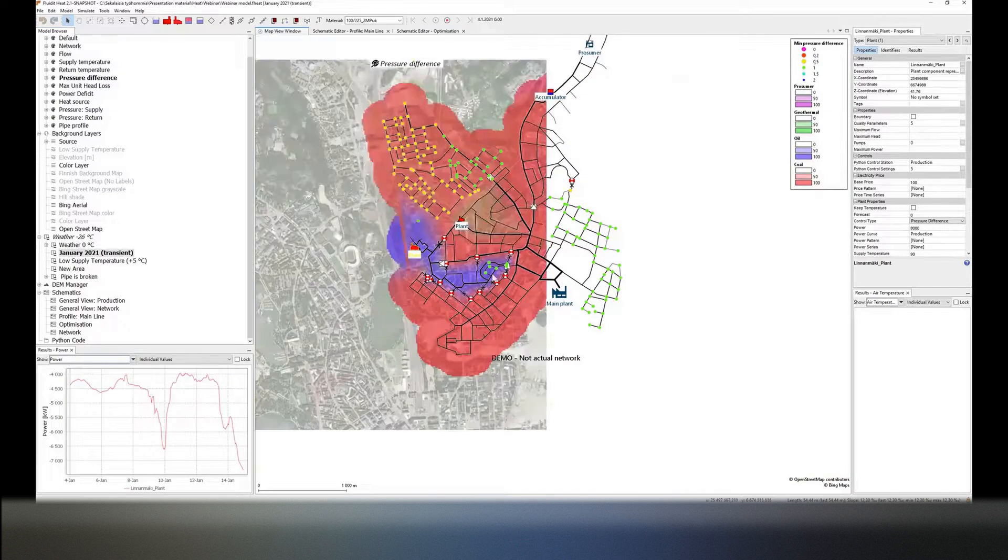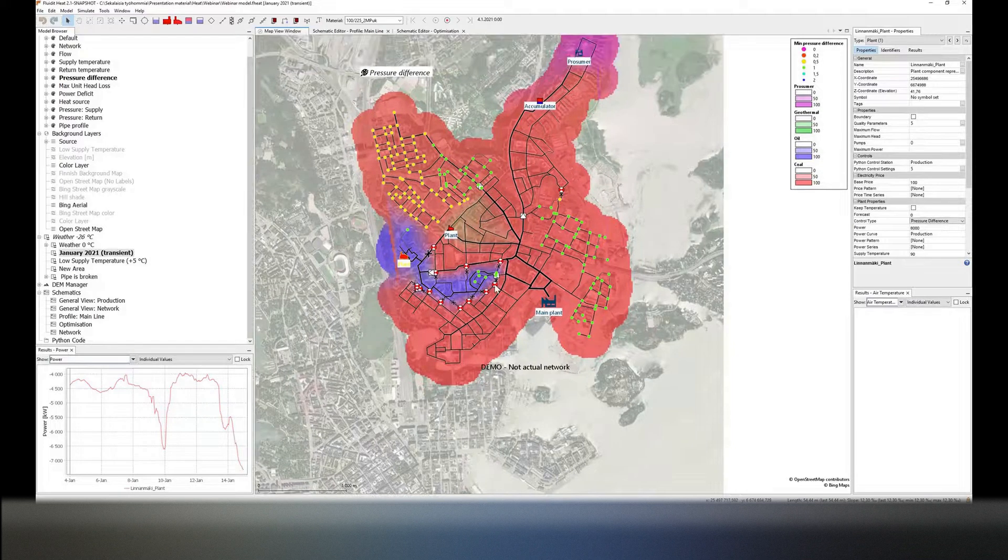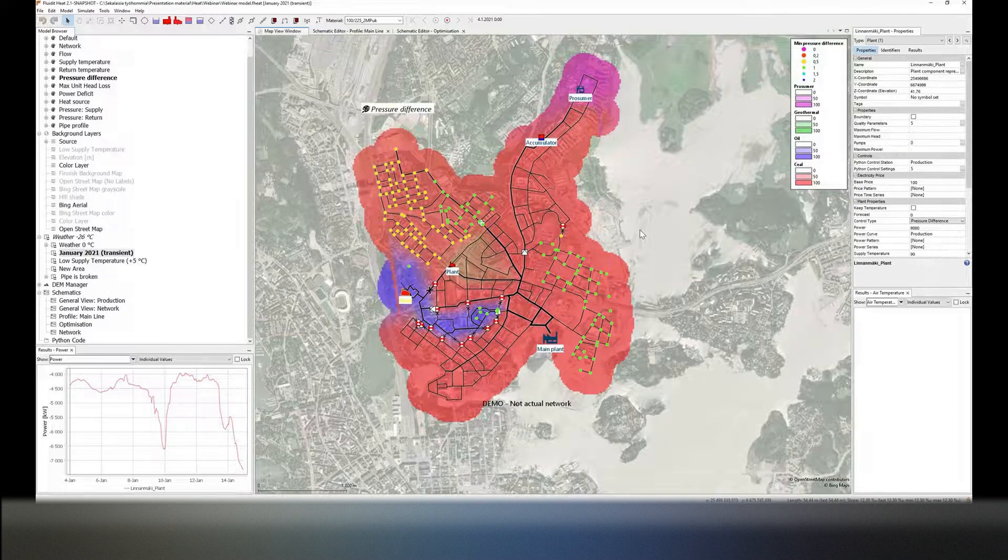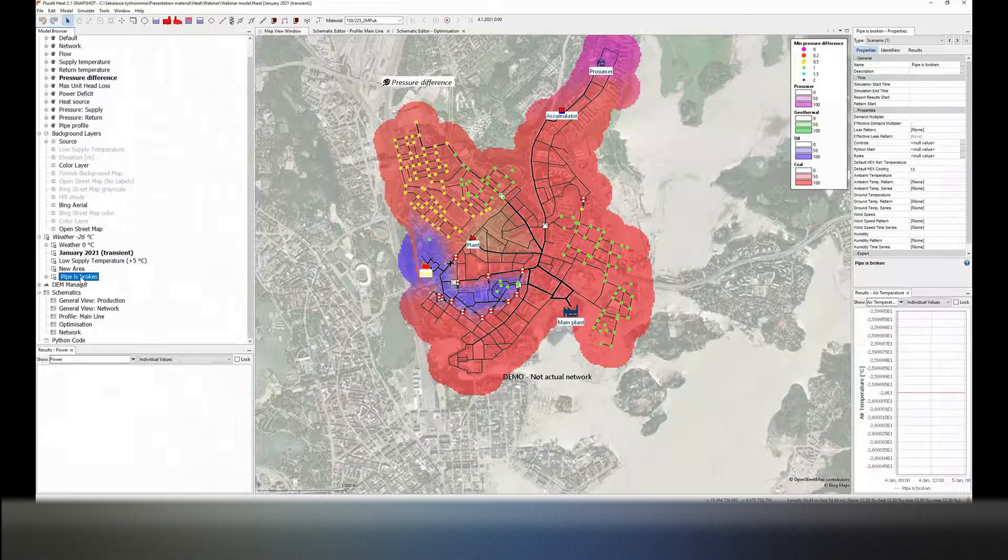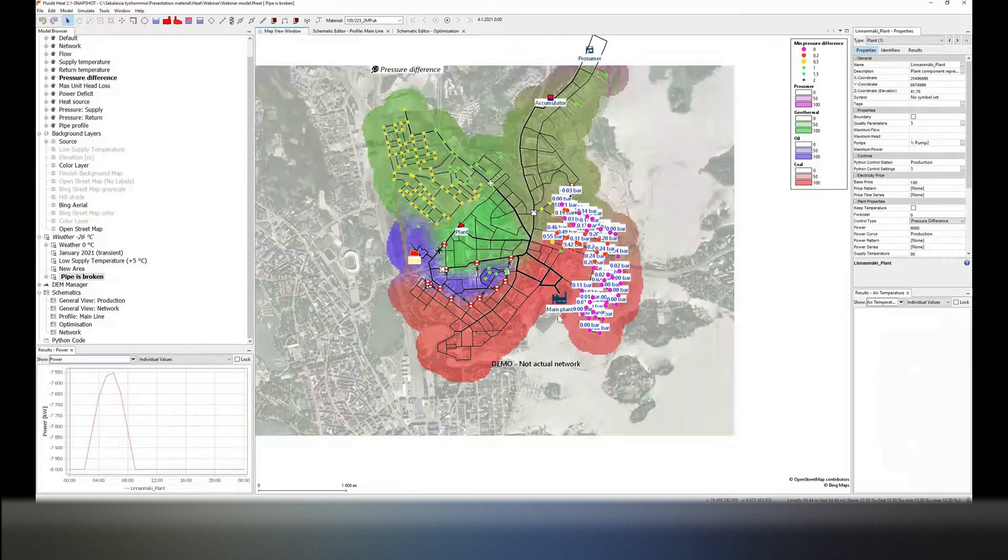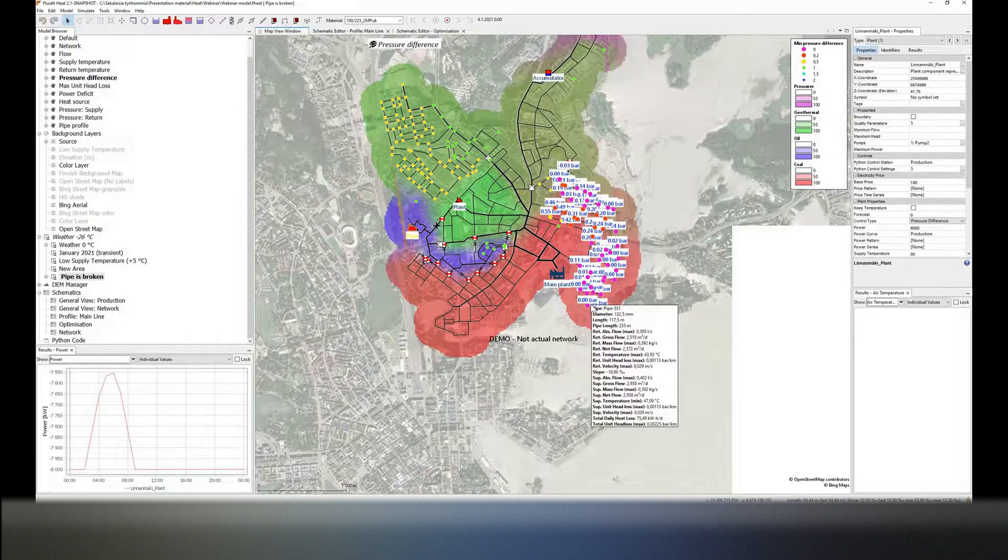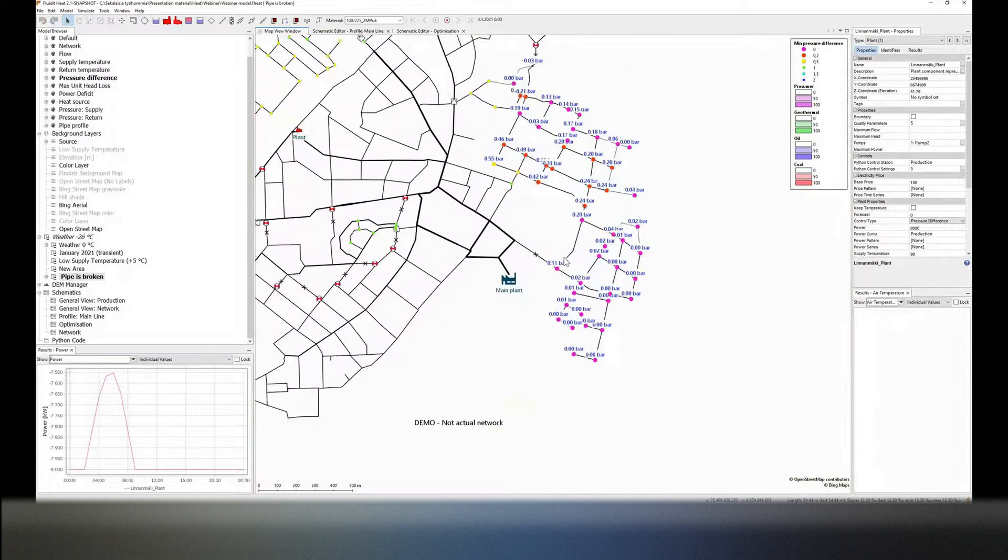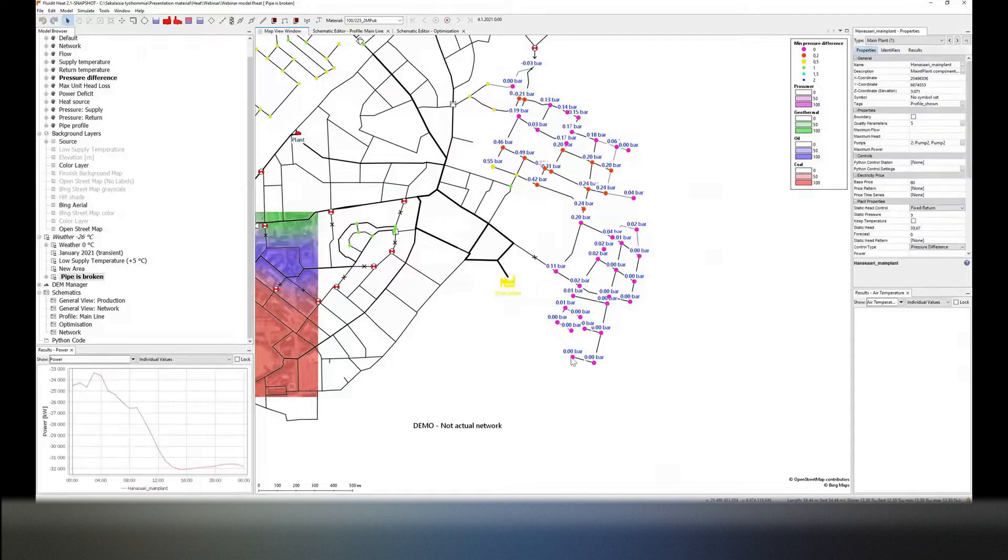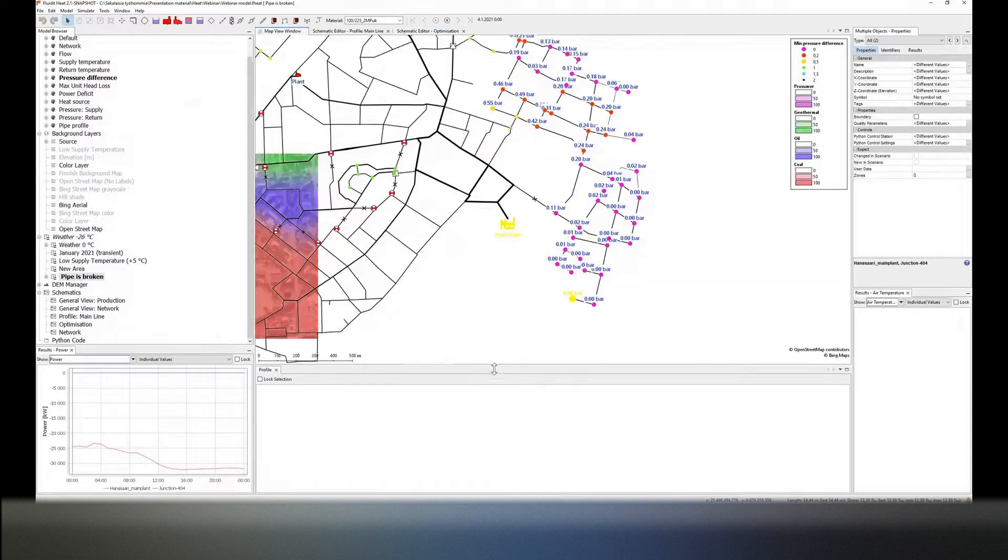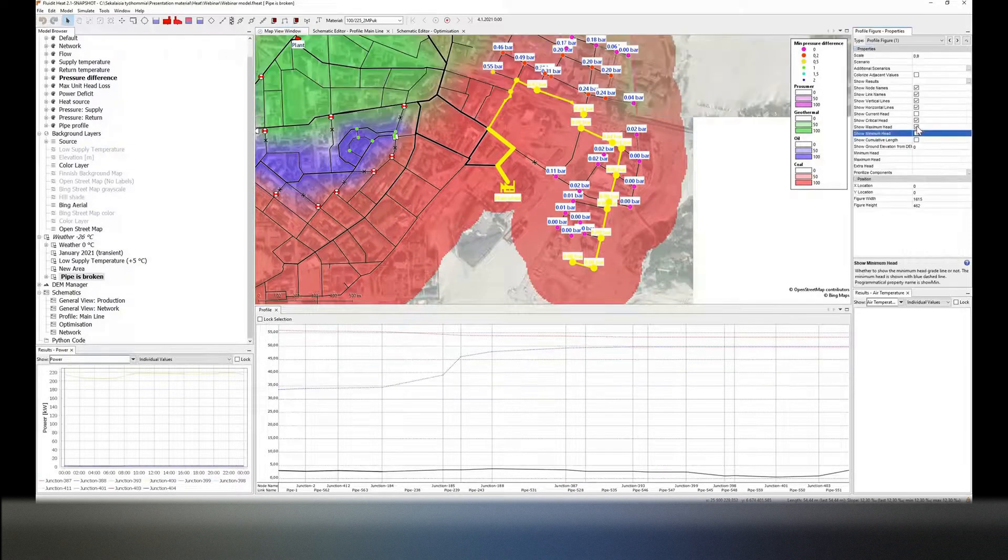Then I would like to show just a little one topic that was especially mentioned - the crisis management. How can FluidHeat be also used for crisis management? So I have created one scenario here - this pipe is broken. And once I go into that, I will be able to see that now the minimum pressure differences in my network is experiencing quite low pressure differences and it's causing problems for the consumers to be taking their power. This is caused by this pipe here being closed, so now all of the water that is going from our main plant to this point is having to go through a different route as it would normally go through here. Here is a profile view of this exactly.